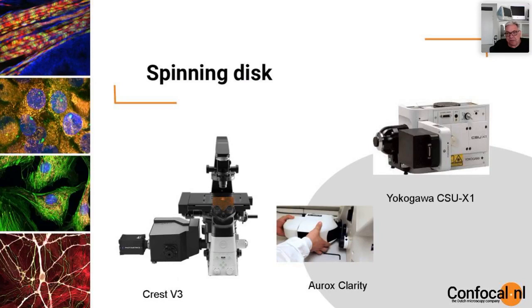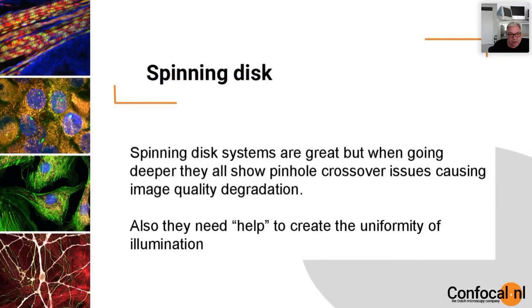Some of these systems are very good — the Yokogawa spinning disk in particular has been extremely successful over the years. It can go very fast, but spinning disk systems have one problem: when they go deeper they show pinhole crosstalk issues. This means they are excellent for flat living cells, but if you have something deeper like an organoid they struggle to maintain good image quality. Also, because of the design of the spinning disk, they all need some help to create uniformity over the field.